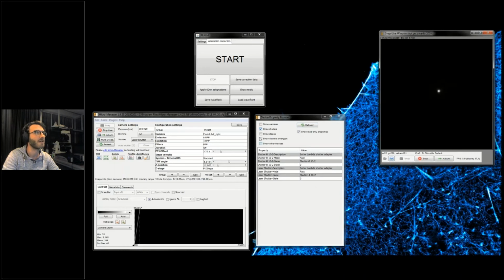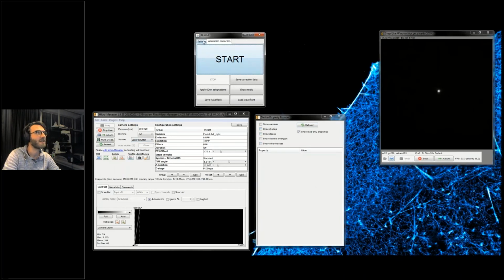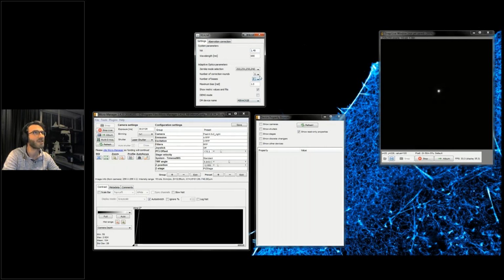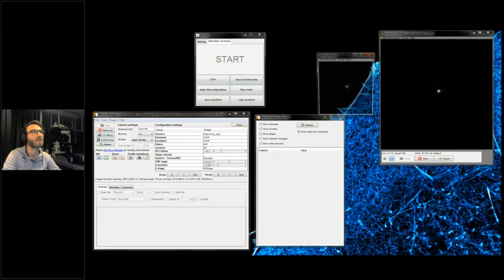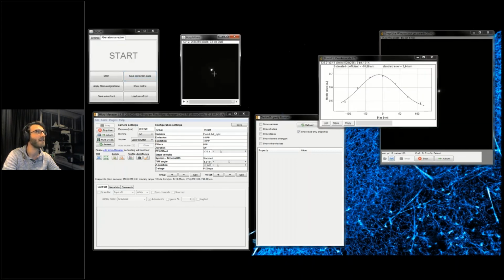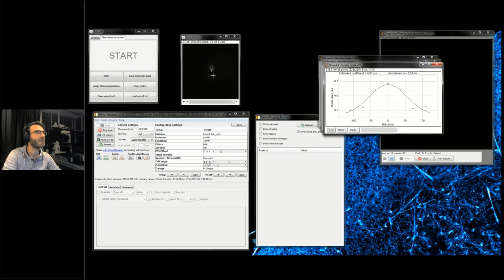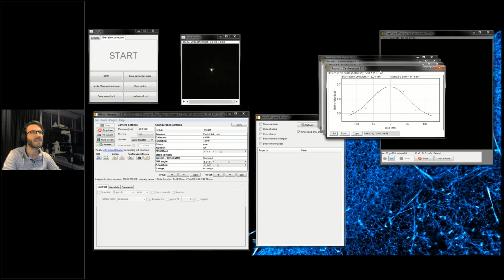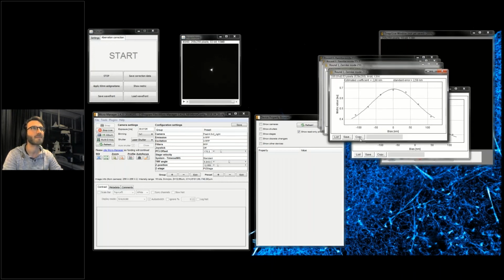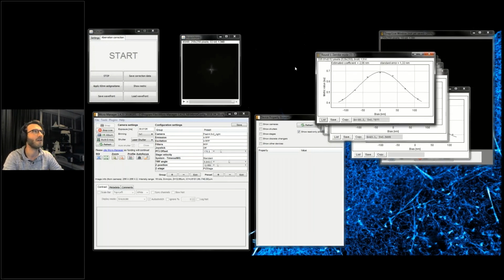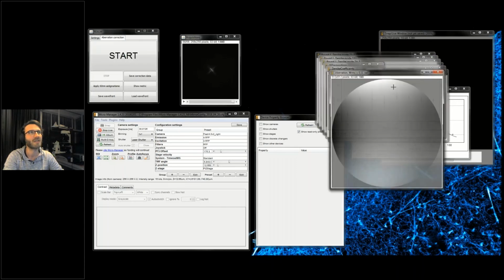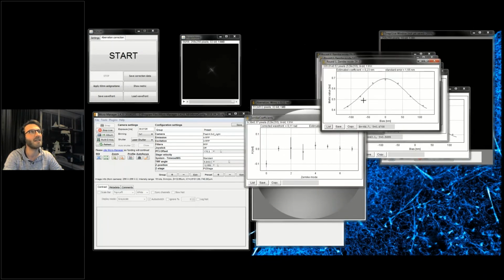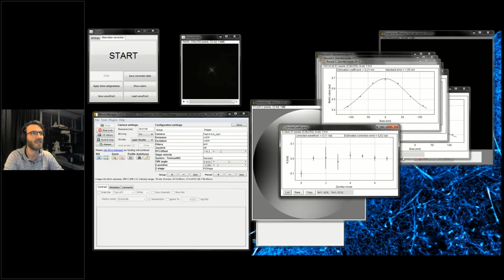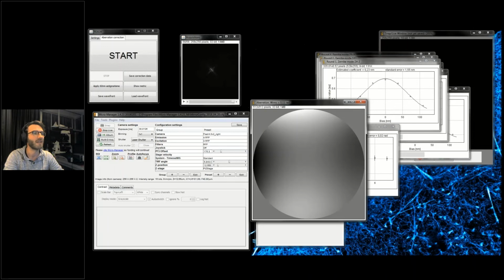In this case, maybe I can use 7 biases in just one correction round, and then start. Here you can see that it starts introducing a lot of aberration, and then shows the specific fits of each metric curve. The better this resembles the curve, the more precisely you can estimate the center, or the correction value. It also spits out the estimated Zernike coefficients and the estimated wavefront profile.